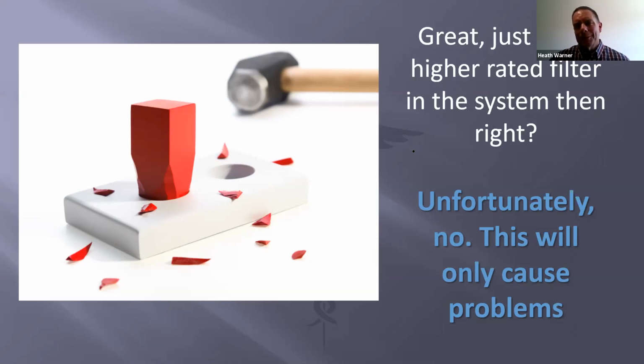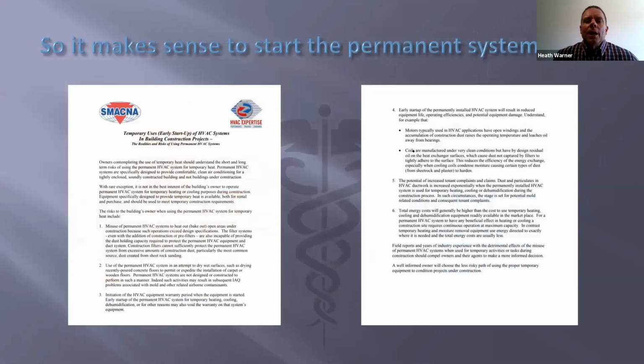But the next most common conception while we're there: most people think, well, hey, the system's designed for a MERV 8, we'll just throw a MERV 12 in it and we'll capture everything. It's the same thing as trying to pound a square peg into a round hole. A system that's designed has to breathe at a certain level. If your permanent HVAC system is designed to breathe through a MERV 8 filter, and you try to choke it off and restrict it, like with a MERV 12, you've effectively cut off probably half to 65% of the air, depending on how far you go with your filter. Ultimately, you're just going to end up freezing up your coils and having problems. Some pictures here in a minute of that.